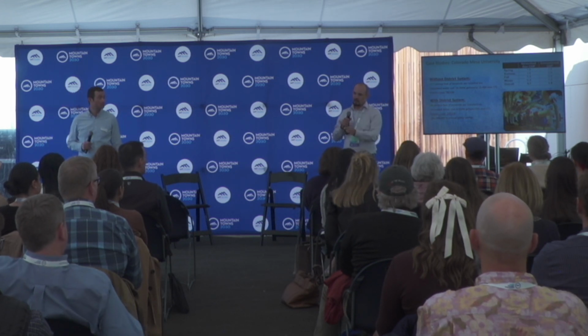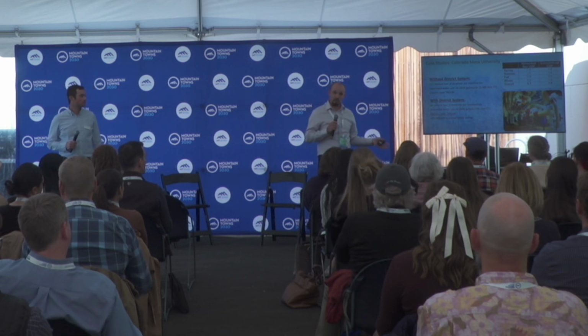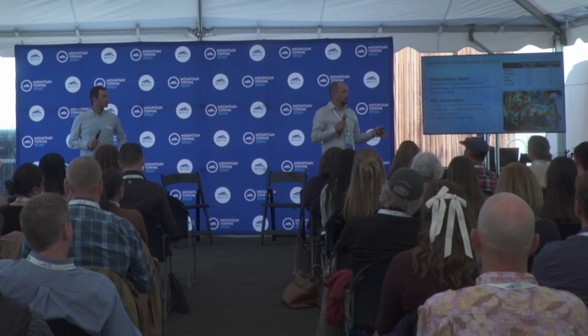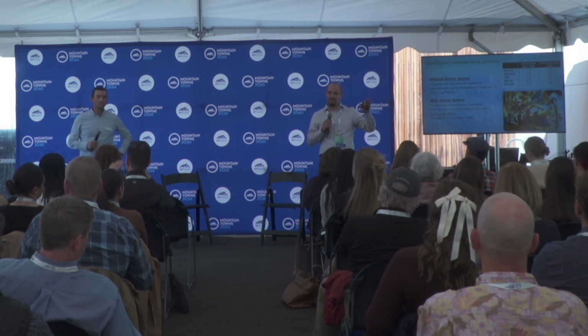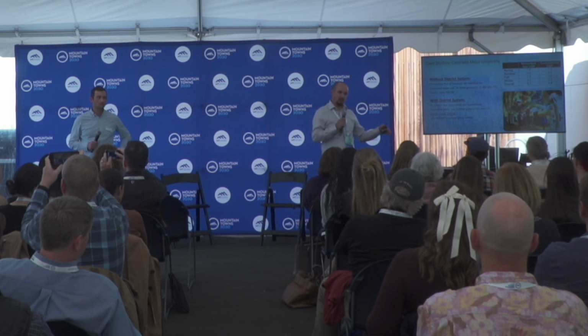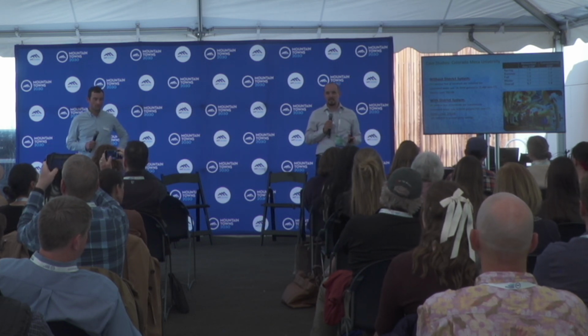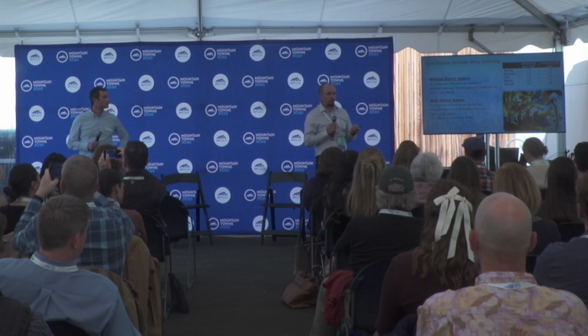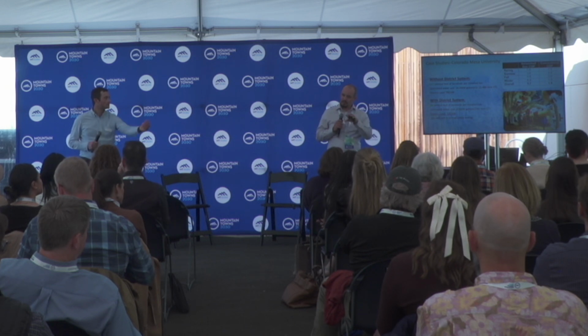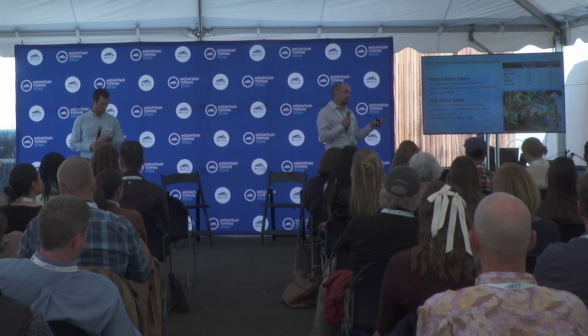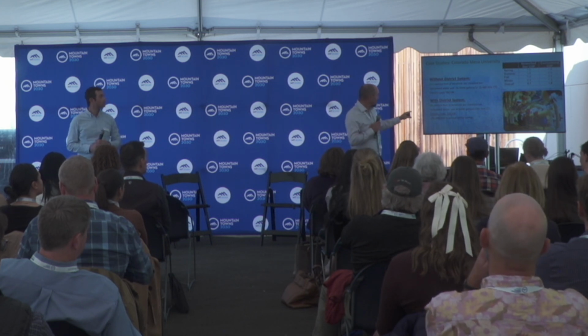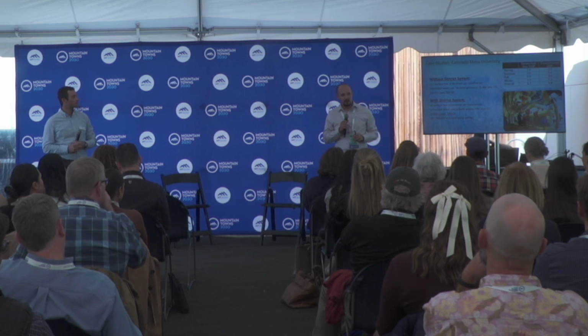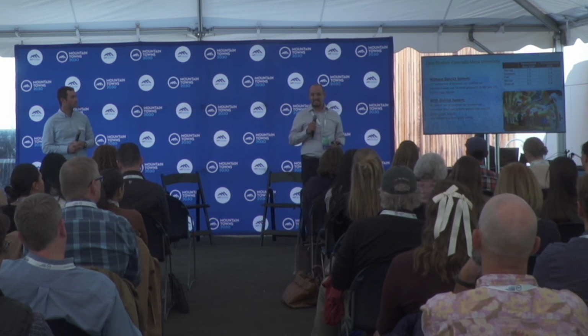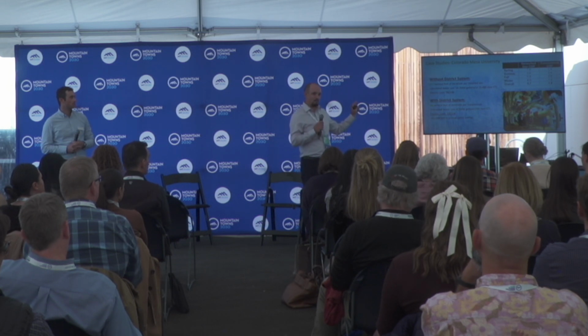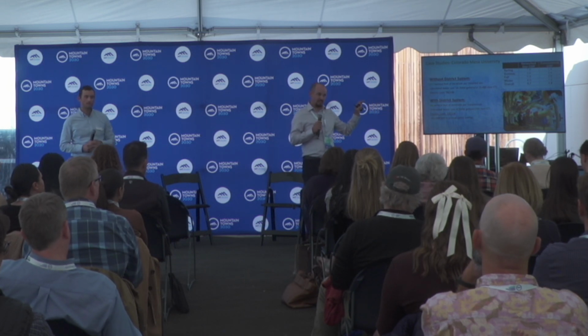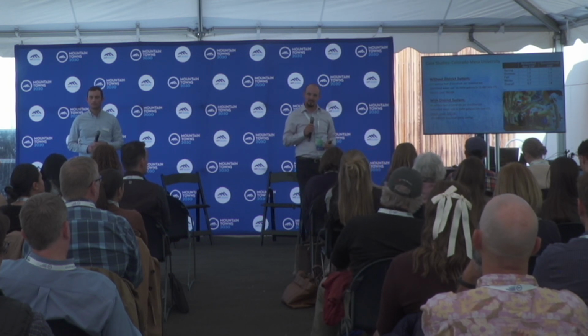If you were to do a one-to-one geothermal installation, like you're probably most familiar with, a geo-exchange system, you would have put in this geology 217 feet of borehole per installed cooling ton. Because of the diversity among the system, because of a more refined understanding of the properties of that ground battery, how fast you can charge it, how fast you can discharge it, how long you can store energy in it, we're able to get away with 84 vertical feet of borehole per installed ton. It's a 61% reduction. And you should read CapEx reduction there. 61% fewer boreholes that need to go in to satisfy this system.